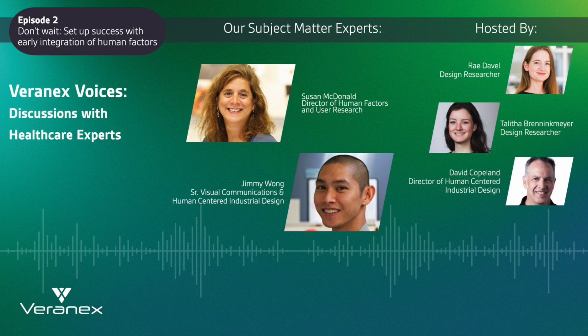Completely, Jimmy. I would just say that FDA is not prescriptive when it comes to design. They're never going to say this should have a button or this should have a latch. They will say, does the button require an amount of force that people are able to impart? Do people understand when they press the button that it has been pressed fully and correctly, or whatever feature, insert feature here. So I feel like that gives a huge amount of leeway on the design side.